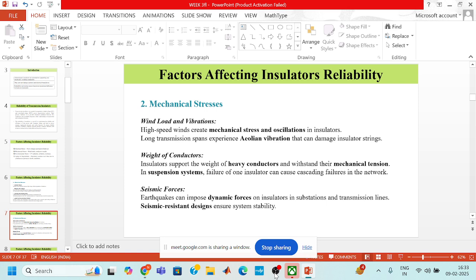Now the second factor was mechanical stresses due to wind load and vibrations. As we know, high speed winds create mechanical stresses and oscillations in insulators. Long transmission spans experience Aeolian vibration that can damage insulator strings. Second is the weight of the conductors. Insulators support the weight of the heavy conductor and withstand its mechanical tension. In a suspension system, failure of one insulator can cause cascading failures in the network due to the weight of the conductor, which causes mechanical stress.